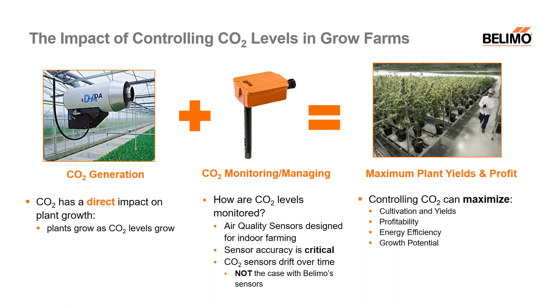Here at Belimo, we offer CO2 sensors designed specifically for the grow farming environment that include technology to effectively eliminate this drift and relay accurate measurements throughout its product lifetime. We've also increased a measurement range within our CO2 sensor product line designed specifically for grow farming. So again, as a farmer, if you can control and fully monitor your CO2 levels, you can really maximize your growth potential, which will then turn into maximum profitability in the future.